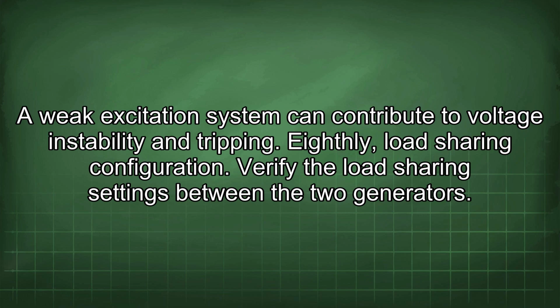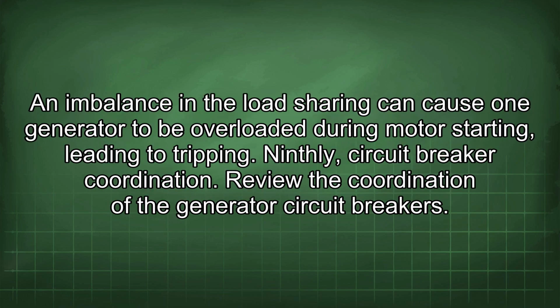Eighthly, load sharing configuration. Verify the load sharing settings between the two generators. An imbalance in the load sharing can cause one generator to be overloaded during motor starting, leading to tripping.